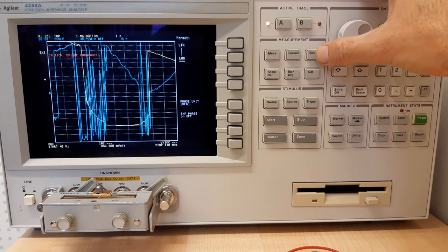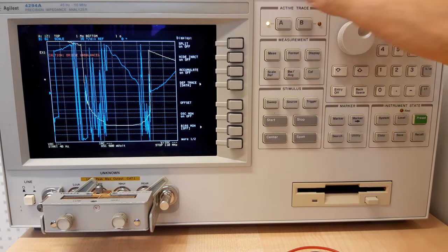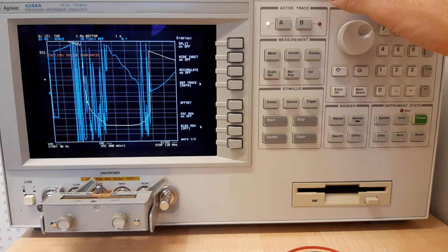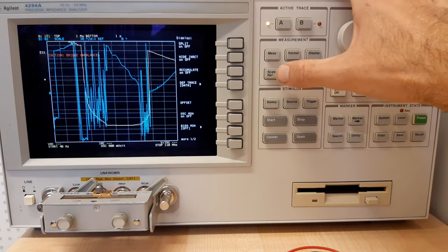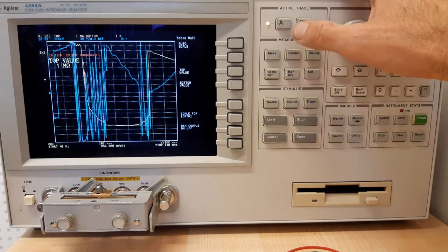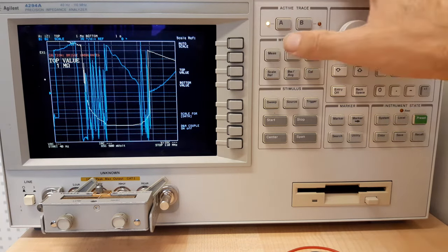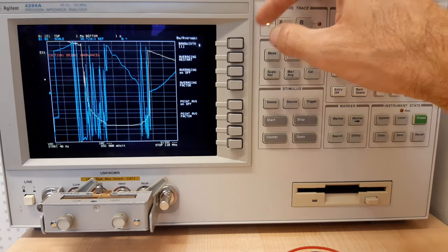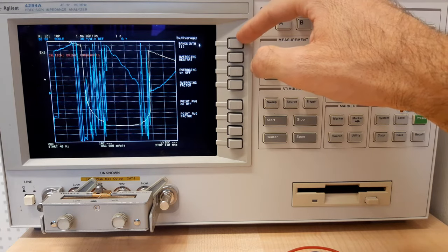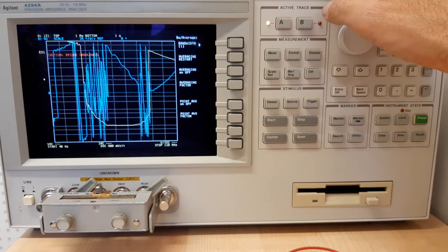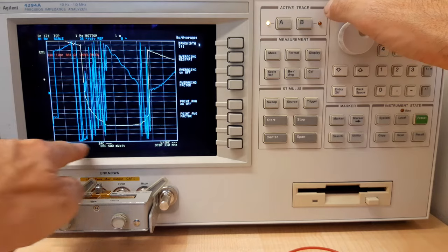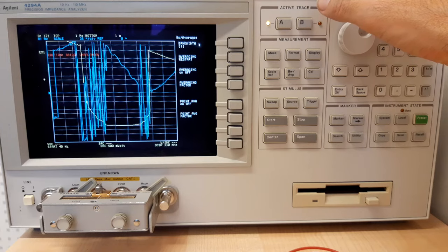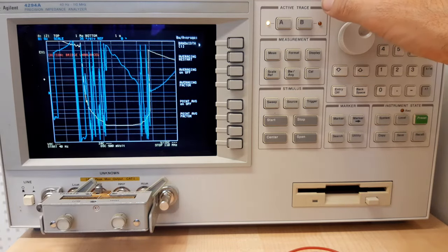With the display button you can go to different display settings; we'll leave it in the basic setting showing both curves — magnitude and phase — in the same diagram. The scale button we'll use later with auto scale. The BW button sets bandwidth and averaging, which controls measurement precision. Setting it to 1 is fast but not very precise; setting it to 5 is very precise but takes more time to complete the sweep.